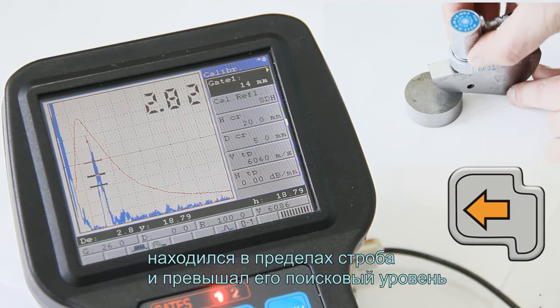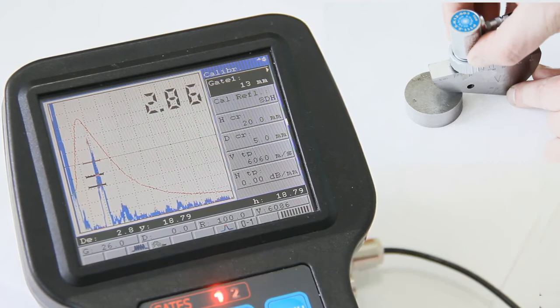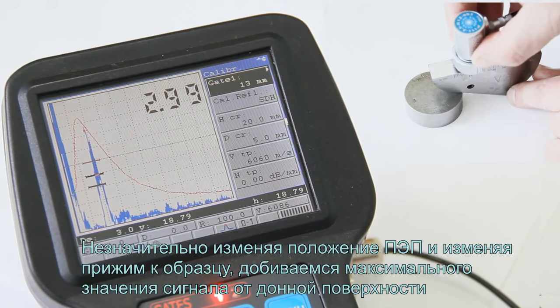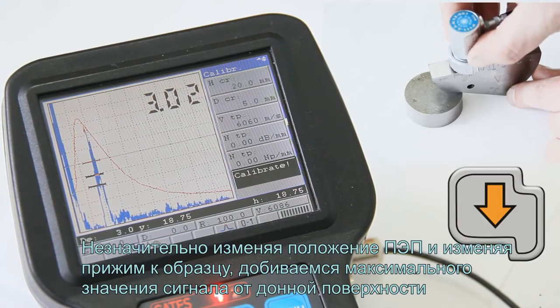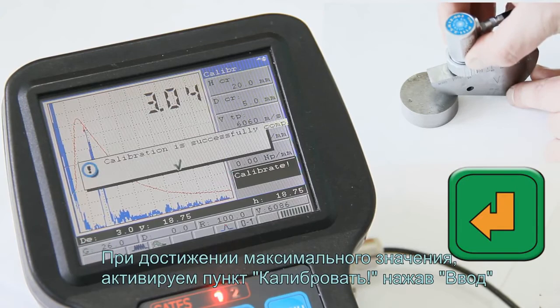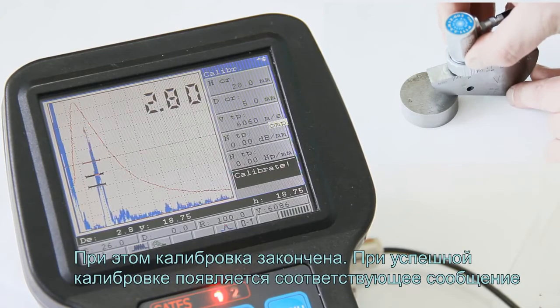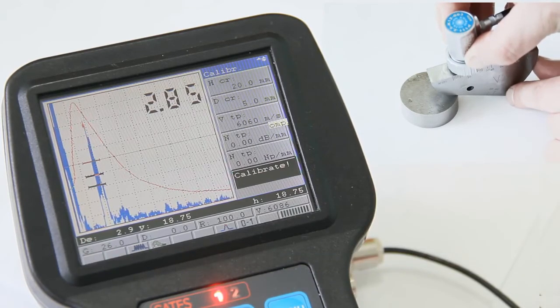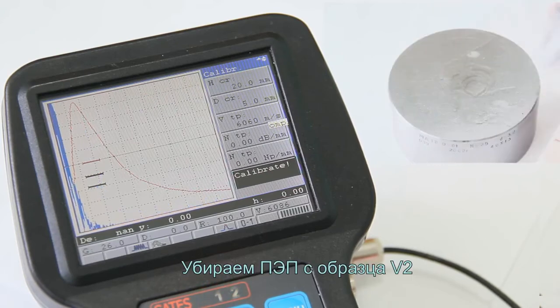Slightly change the probe position and change the probe pressure to the block to achieve the maximum backwall echo. Having achieved the maximum value, activate the calibrate item by pressing the Enter key. The calibration is finished. In case successful calibration, the following inscription is appeared. Remove the probe from V2 block.